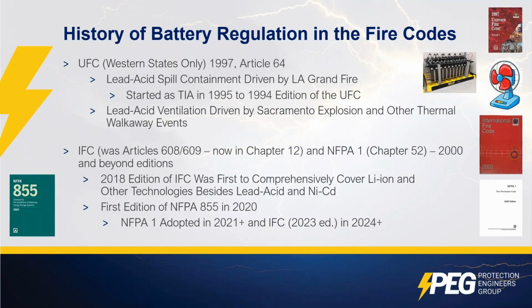Each had their own fire code, and one of the early recognitions was that lead acid batteries, as used by the telecom industry, clashed with the codes. The code people wanted to treat the large amounts of lead acid in batteries as a hazardous occupancy. If you strictly applied the code, that would have been how it was treated. But the argument was, well, these aren't really that hazardous. They're in a special use. They're important to the telecom network. So they reached a compromise.